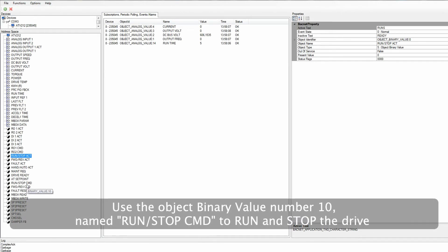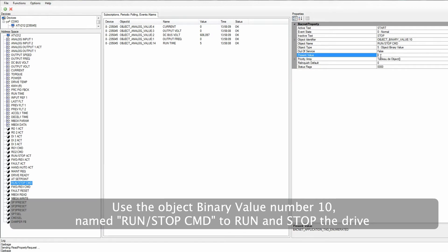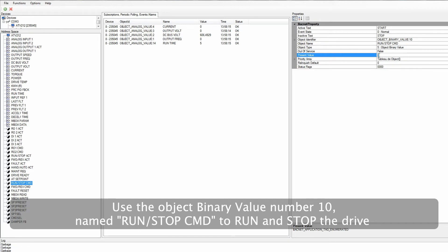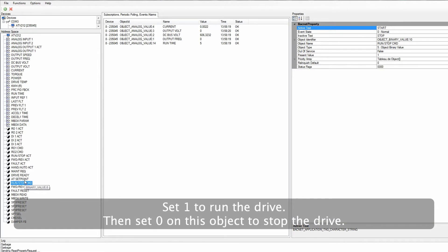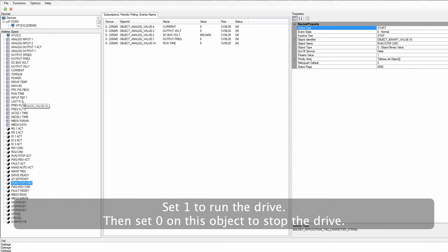Use the object binary value number 10, named Run Stop Command, to run and stop the drive. Set 1 to run the drive. Then set 0 on this object to stop the drive.